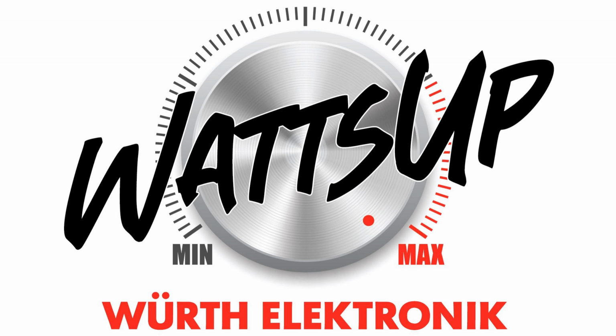The sectional winding has the advantage of withstanding a higher rated voltage, because the wires are simply further apart from each other. So insulation is not that critical, and we can reach higher rated voltages. But on the opposite side, the stray inductance is higher, because the further apart the windings are, the lower the coupling, and the higher the stray inductance. So it can go up to 5% at maximum.